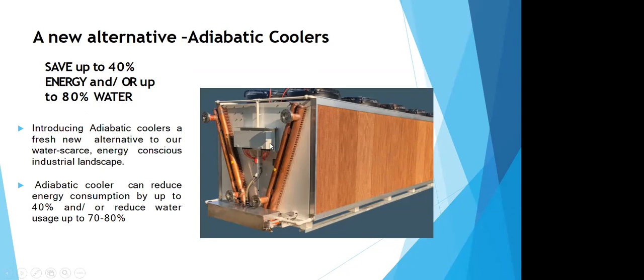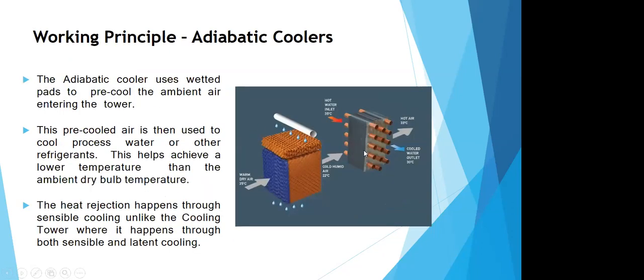Now, how does it work? It's simply an air-cooled heat exchanger. We have two sets of coils which are arranged in a V shape, and you allow the condenser water to flow into these coils coming from the chiller. And the fluids within the coil can be cooled by the air which is sucked in from here and is drawn out. And there is a pad in between which is used to pre-cool the incoming dry air. So the adiabatic cooler uses wetted pads to pre-cool the ambient air.